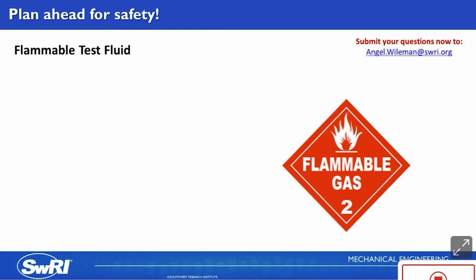The last safety hazard that I want to discuss is the flammable test fluid. If you're testing with methane, the flashpoint temperature is really low, and so you're constantly off-gassing flammable vapors. To minimize safety risks of working with methane, the testing should be conducted in a well-ventilated area, with outdoor testing preferred.